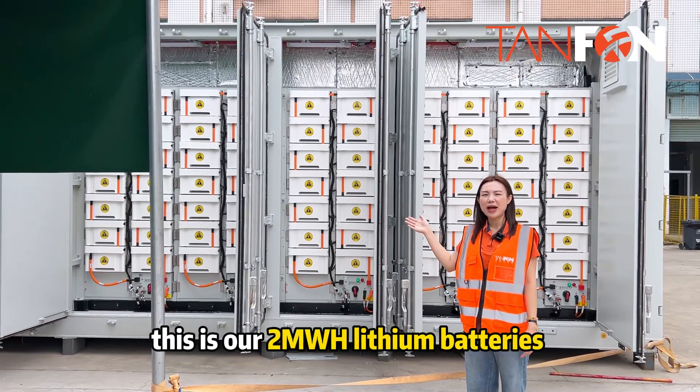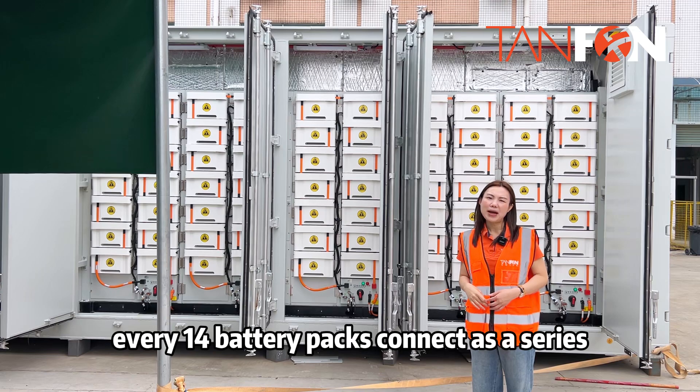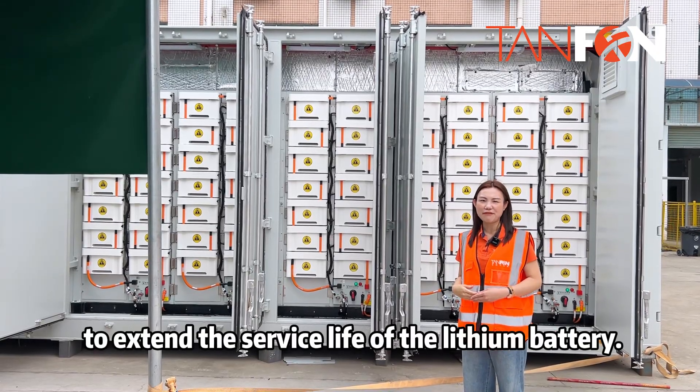This is our 2MWH lithium battery housed in a 40-foot container. They have a total of 140 battery packs, with every 14 battery packs connected in series. The temperature of the container can be controlled by the EMS to extend the service life of the lithium battery.